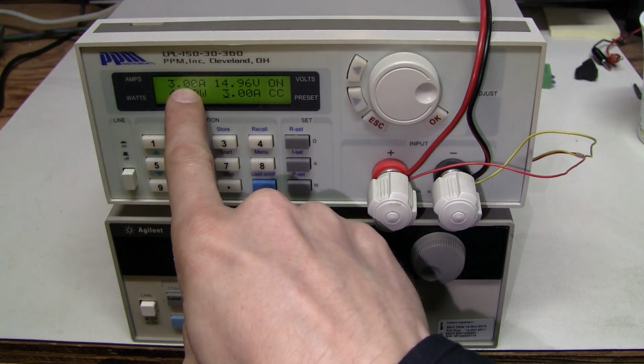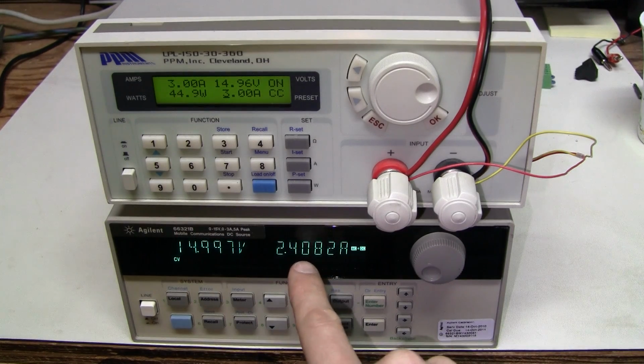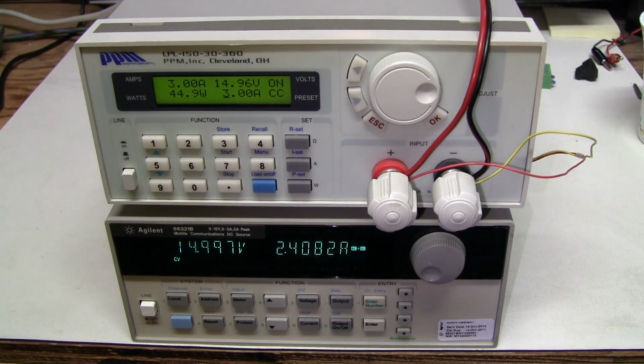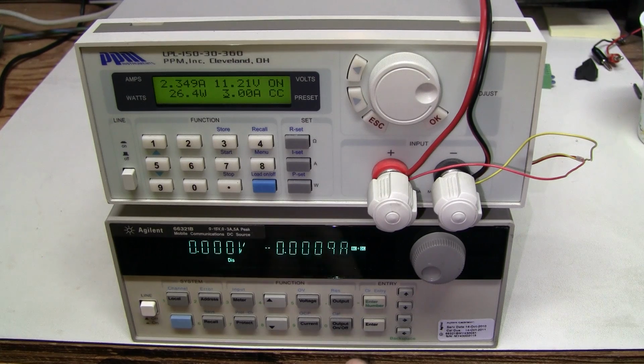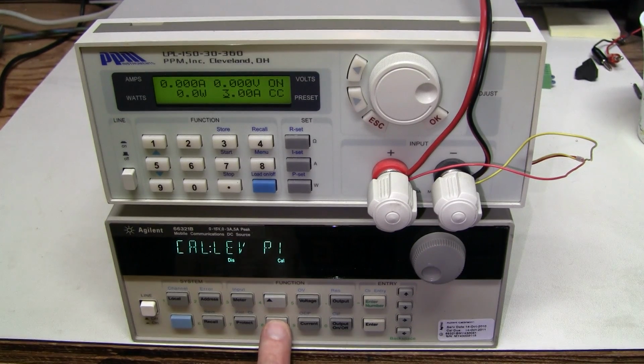It gives exactly 3 amps out, but again the current reading is wrong. We need to calibrate it as well. So let's try calibrating this. Let's disable the output, go to the calibration mode and select the current calibration. Here it is.